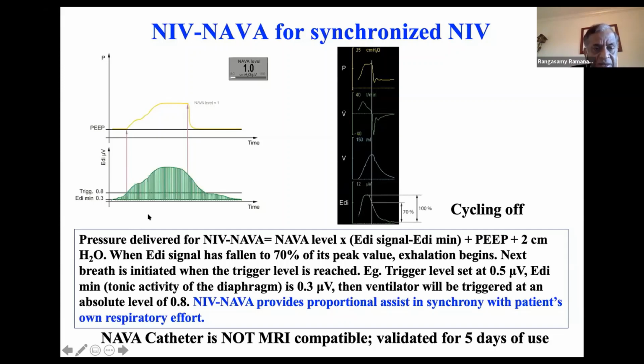This is the EDI graph, and this is the pressure over time graph, in seconds. When the EDI signal has fallen to 70% of the peak value, the machine cycles into exhalation. The trigger level is the EDI trigger. The minimum EDI measured in this baby was 0.3 microvolts, and you set the trigger at 0.5. So when the diaphragm activity rises above 0.8, the machine will give a breath, triggering. That's how you set it up. As I mentioned, EDI minimum means tonic activity of the diaphragm, so the ventilator will be triggered at an absolute level of 0.8.